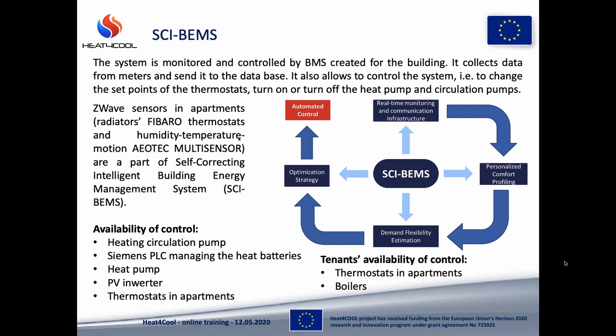So the self-correcting intelligent building energy management system, shortly SciBEMS, was implemented in the building to collect the data from meters and send it to the database and to control the system. In the building, we can control the work of the heating circulation pump, the PLC, which manages the heat batteries, the work of the heat pump, the photovoltaic installation, and thermostats in the radiators in each apartment. But the thermostats can also be operated manually by the tenants, the same as the set points of the boilers. And if there is a change, the system will adjust to the new settings, respecting energy efficiency.